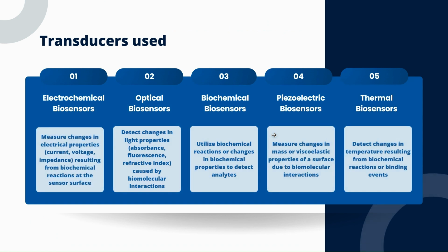Next, we see what are the transducers used in these different biosensors. First is the electrochemical biosensor. Electrochemical biosensors measure changes in electrical properties such as current, voltage, impedance resulting from biochemical reactions at the sensor surface. They typically consist of a working electrode, a reference electrode, and sometimes a counter electrode. The biological recognition element immobilized on the working electrode interacts with the target analyte, leading to a measurable electrochemical signal.